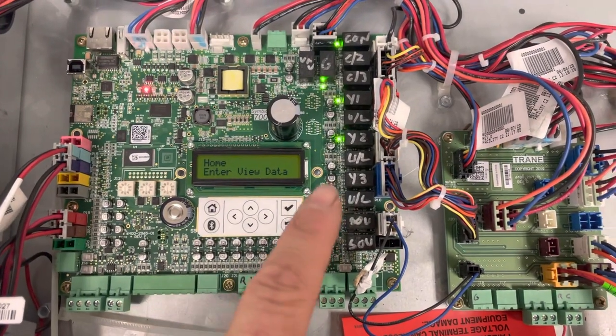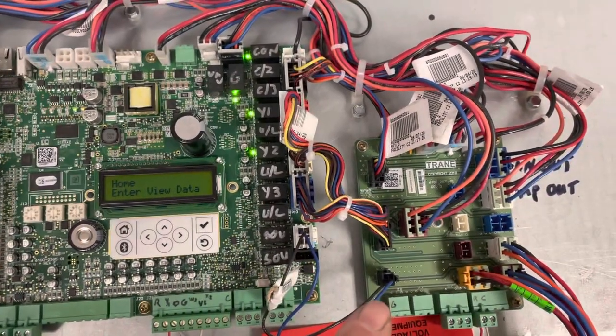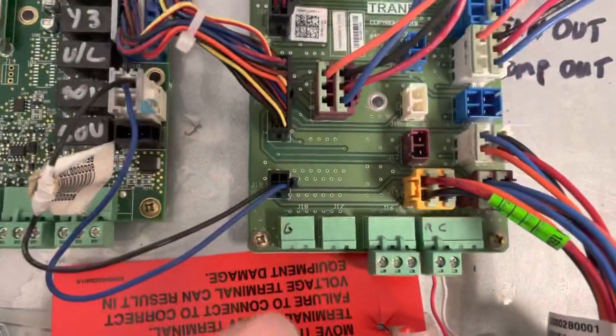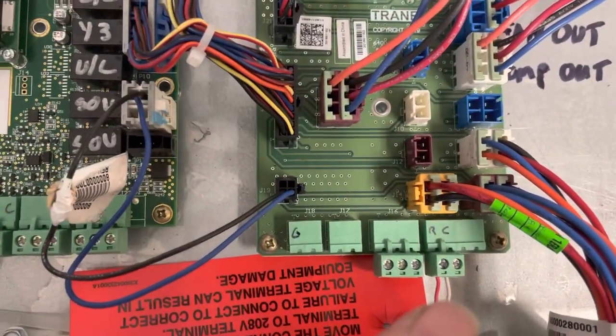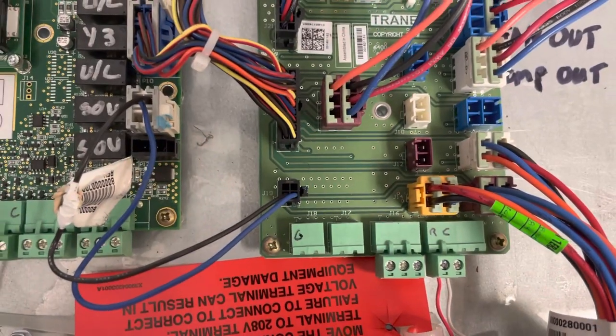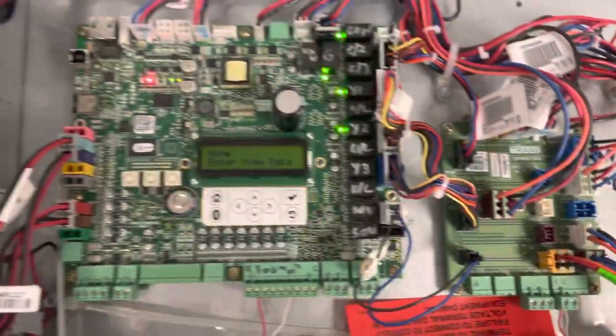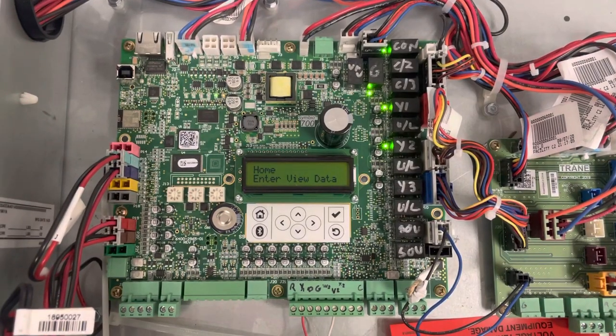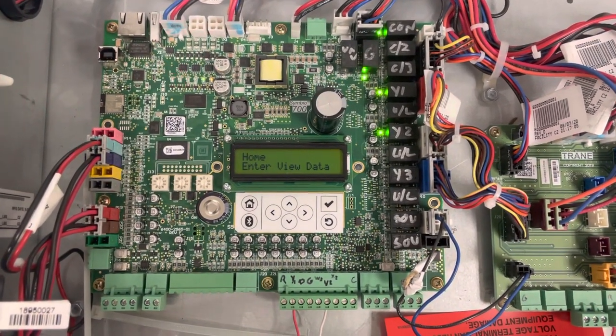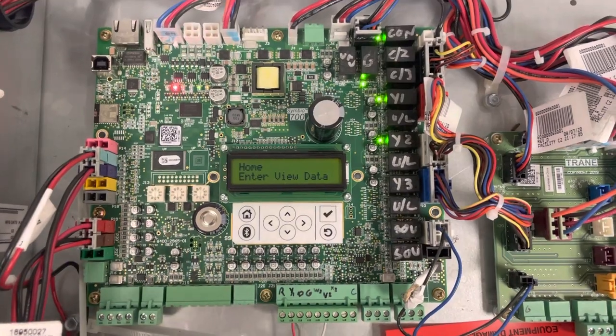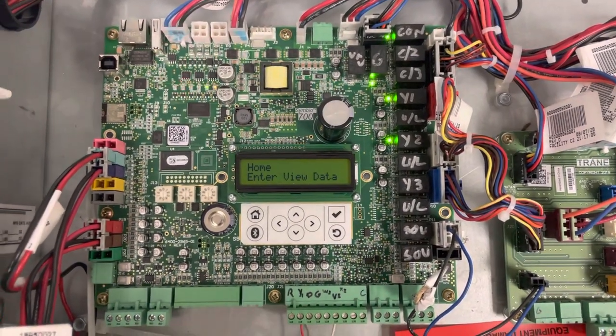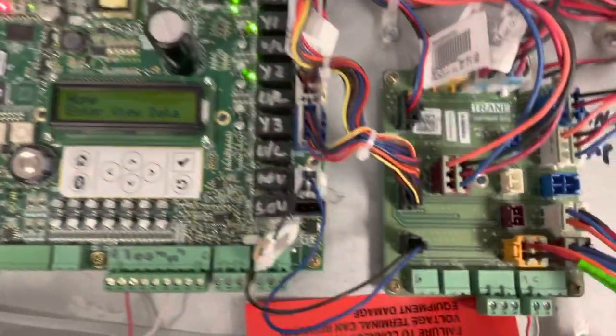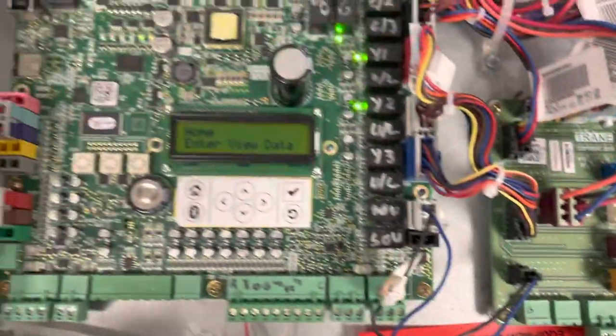And you know, not really using anything over here. You don't need that G output for this configuration. And again, that RC is just to power up my indoor unit. Just a note warning: wiring up this way does kind of defeat some of the logic, some of the protections built into the Symbio unit. What makes it special, we don't have our G signal out so we can't do evaporator defrosts.